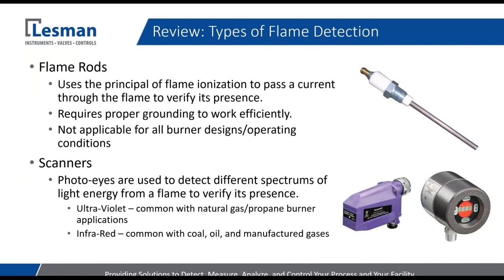We'll do a little bit of a review, going through the common types of flame detection first, because they will have different types of issues and things we'd need to look for to identify why your burner would shut down. The first very common type is a flame rod, which uses the principle of flame ionization to pass current through the flame to verify the presence of flame. The flame safeguard sends out a high voltage signal around 200 volts through the flame rod, and when the flame is present, the current goes through the flame to a burner ground. This requires proper grounding — you've got to make sure you have that current path from the flame safeguard through to the ground.